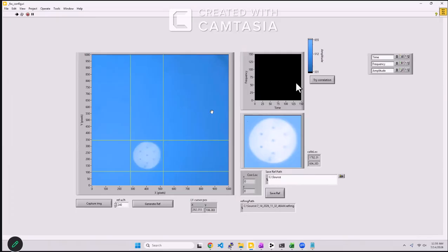Right now, this is like 200 pixels wide. If you change the focal distances or distances of any of these lenses, the magnification will change, which is why we have this setup to obtain and update your reference image very easily, and it's not hard coded into the embedded code. It's because we change our focuses and magnifications all the time. So that's just something to be aware of.